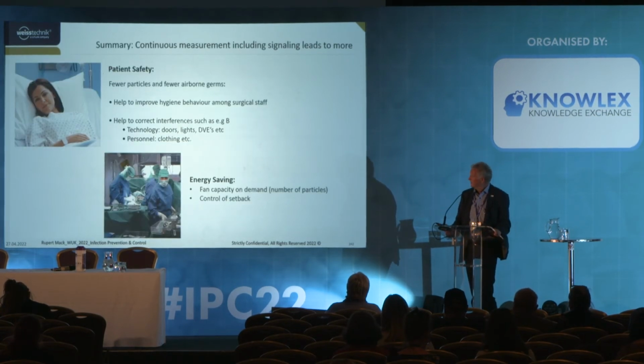From the principle I mentioned, we speed up the fan if the number is higher than 100 particles. 158 is higher than 100. So the system begins to rise up. And the fan activation was 50%, then 53%, and then 65, 74. So that means there is a flexible system reacting on the particles we measure. And we believe that this could be a different way of thinking.